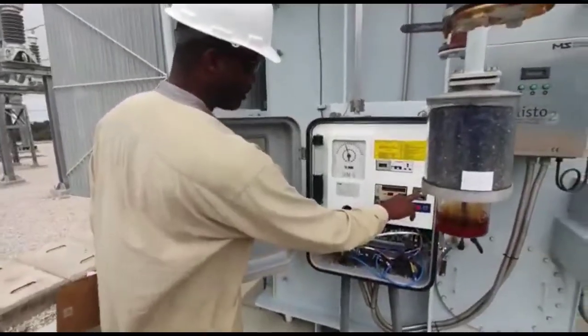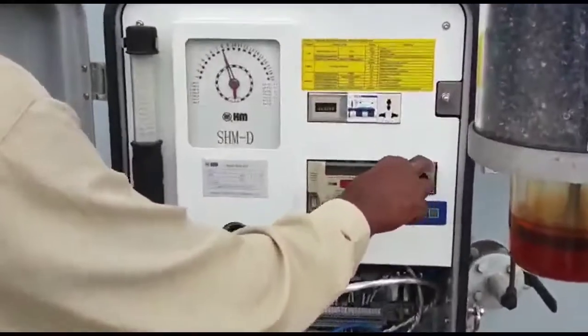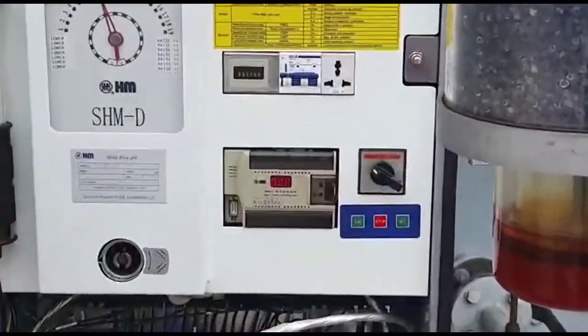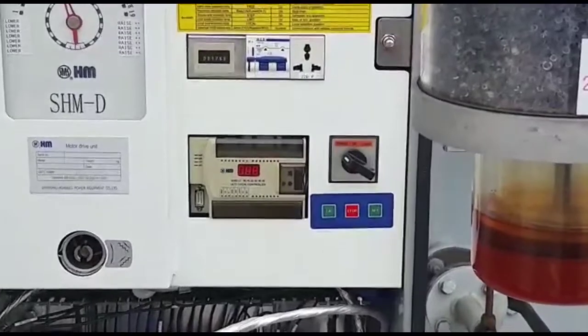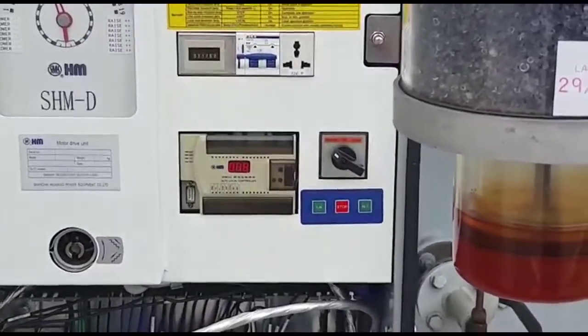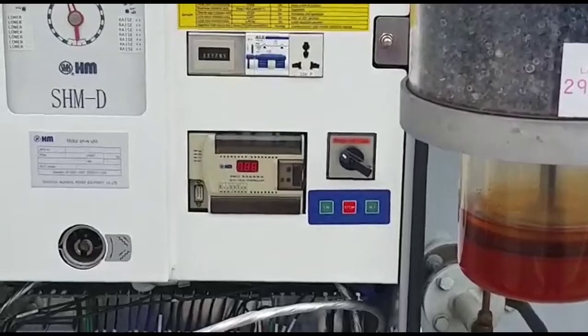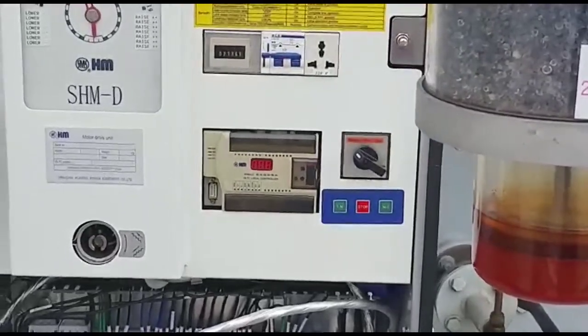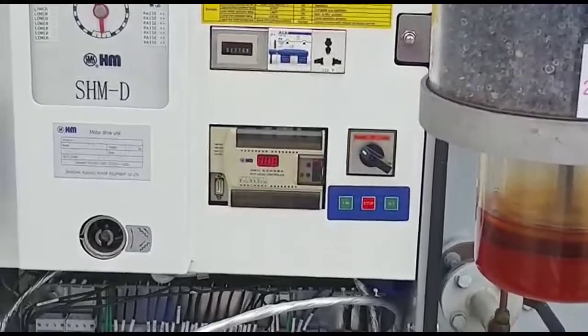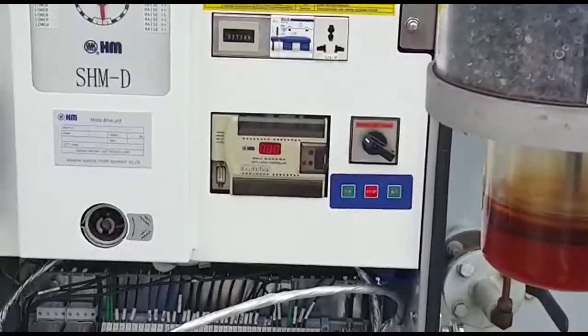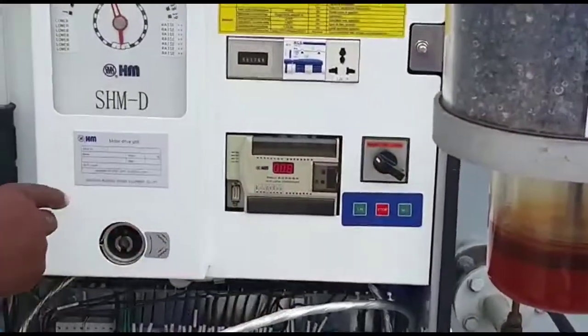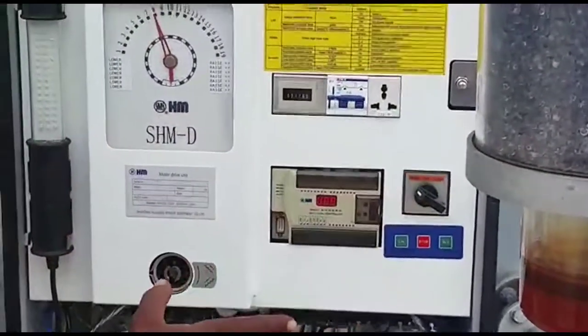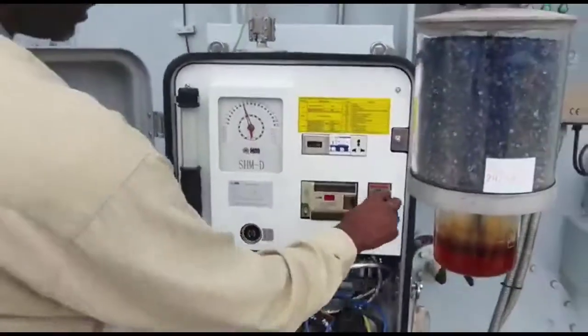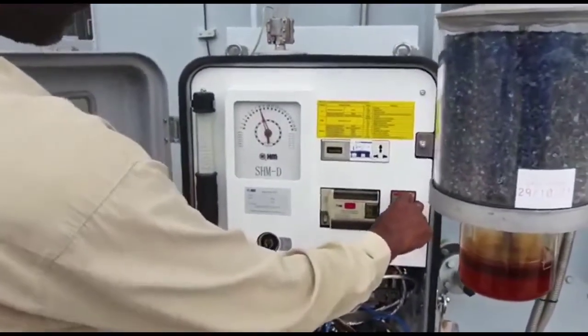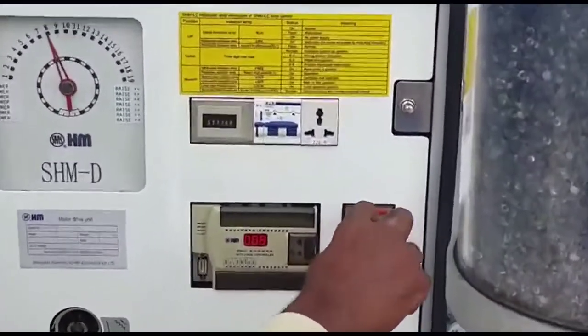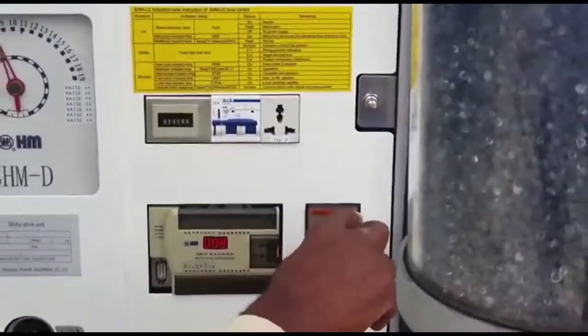Here we have the switch that switches from remote to local. When it's in remote, the transformer will automatically do all that tap setting change by itself. You don't have to do anything. It senses the voltage coming in and going out, and it will automatically change that voltage to keep it in the desired bandwidth of 34.5 kV. When you need to operate this transformer from right here, physically, you need to put this switch into local. That's right here. So you have remote, off, and local. When it's in off, it's not going to operate either remotely or locally.